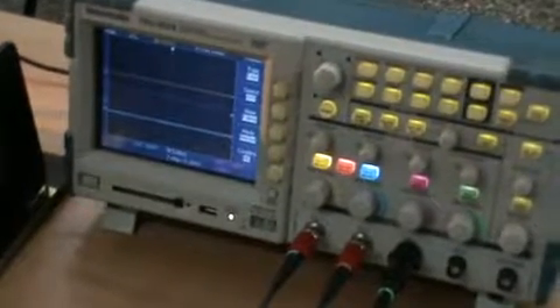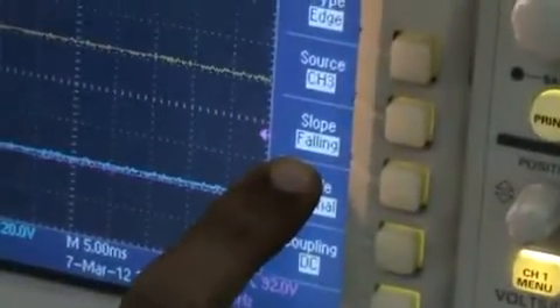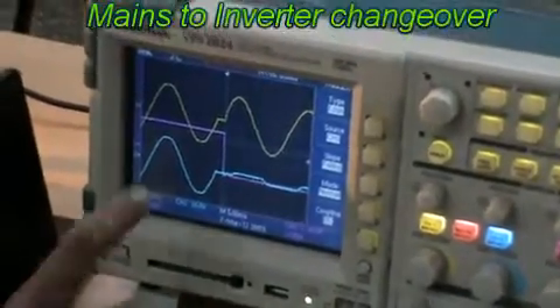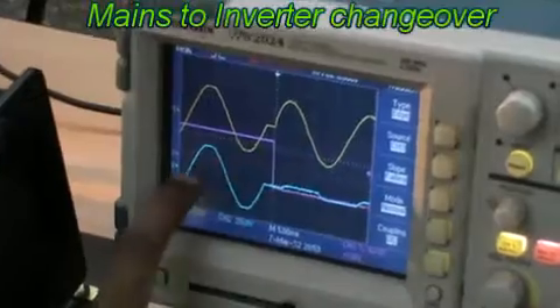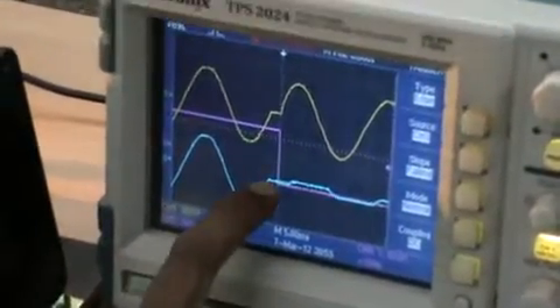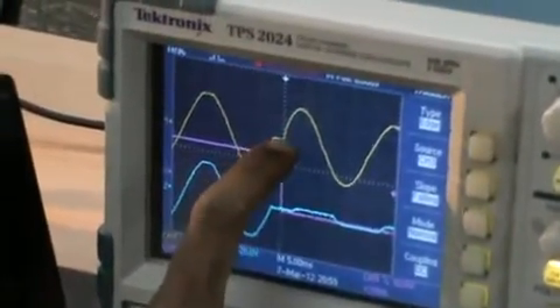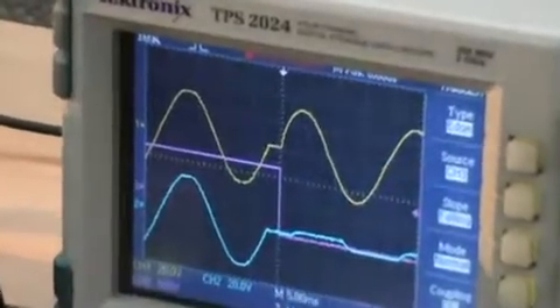Now I am showing from mains to inverter. Now it is in mains mode. So I am going to switch off the mains. You see that falling edge, I am triggering on the falling edge. Earlier it was the rising edge. So now I am switching off the mains. See, the blue is the mains, here mains failure. Then see, the inverter starts from the same point.